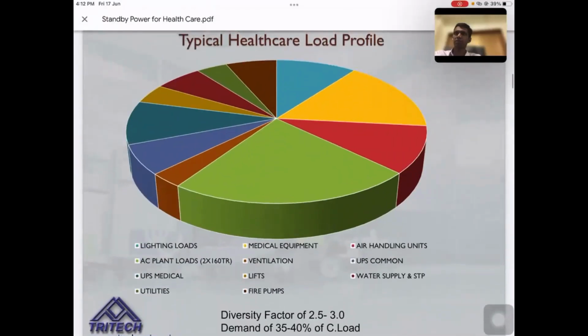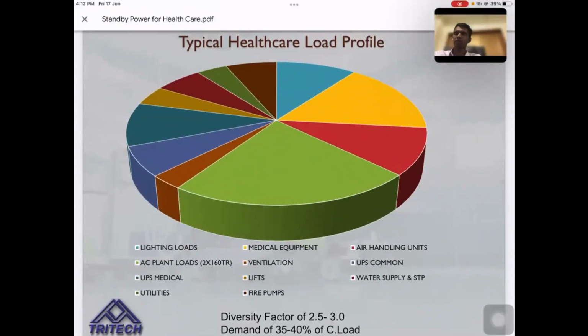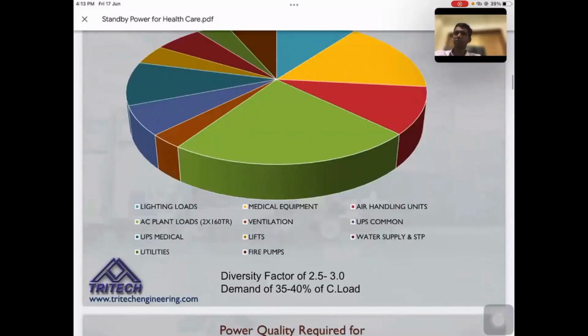And if you look at the typical healthcare load profile, you can clearly see that the majority of the loads are basically the HVAC loads. And of course, the medical equipment, air handling equipment, lighting, the lifts, fire and water pumps. As a general rule, the diversity in hospitals touches somewhere between 2.5 to, this is a very general thumb rule, which needs to be accurately worked out later probably. So you can expect a demand of 35 to 40% of the connected load in most hospital projects. This is why I wanted to highlight this point.